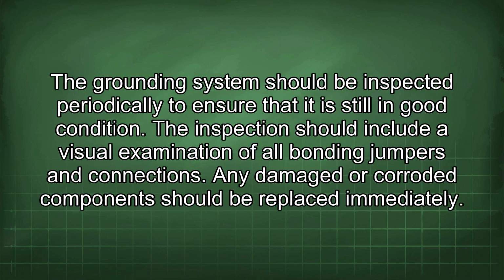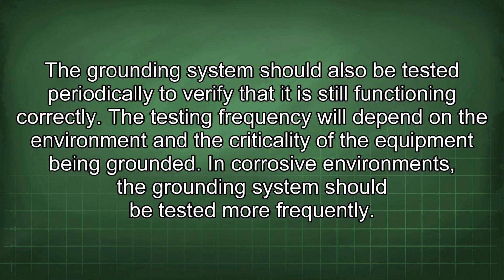The grounding system should be inspected periodically to ensure that it is still in good condition. The inspection should include a visual examination of all bonding jumpers and connections. Any damaged or corroded component should be replaced immediately. The grounding system should also be tested periodically to verify that it is still functioning correctly. The testing frequency will depend on the environment and the criticality of the equipment being grounded. In corrosive environments, the grounding system should be tested more frequently.